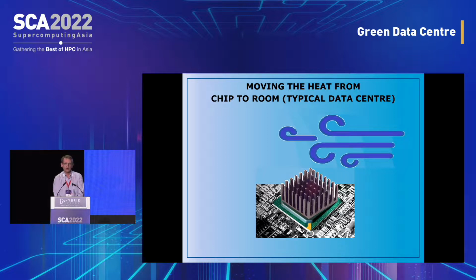No matter how hard we try at designing our heat sinks, we still need quite a big temperature difference between the chip surface and the air in order to get the heat transferred out. Typically we might be looking at a temperature difference of maybe 50 degrees. Every IT equipment has different characteristics, so don't worry about the precise numbers, but the point is you need a very big temperature difference. Because of this, in a lot of data centers we're looking at maybe 25 degree air that has to be blown across to make it work.